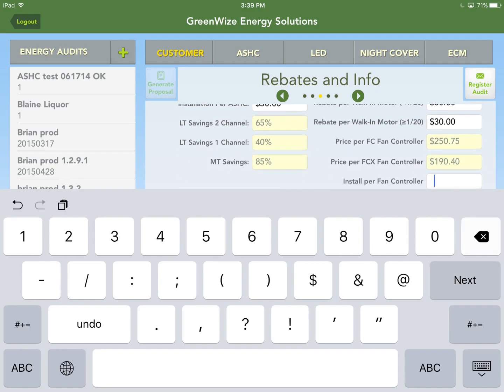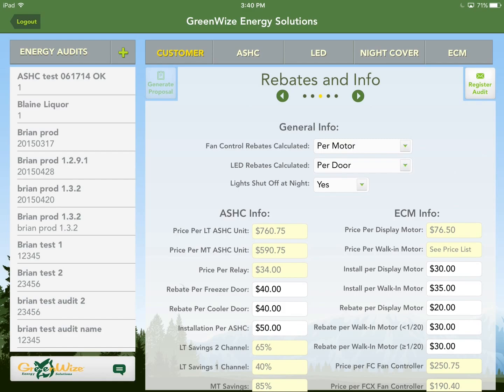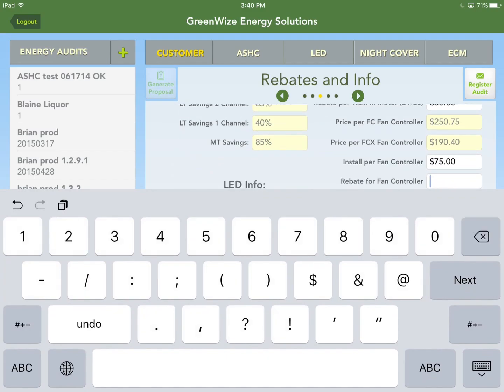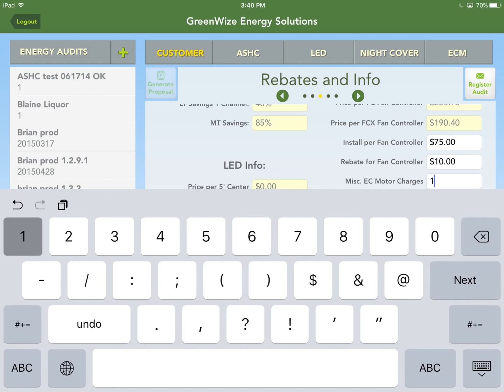Install per fan controller — $75. Rebate for fan controller: since our application calculates per motor, we'll say $10 per motor. For miscellaneous EC motor charges, there's a good chance you'll be swapping old single-speed motors for new two-speed EC motors, which may require extra wiring, wire nuts, and other materials. This field is for an all-encompassing charge for those extras — let's say $100.